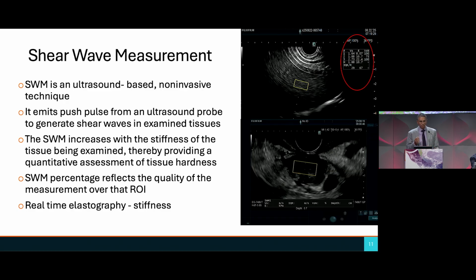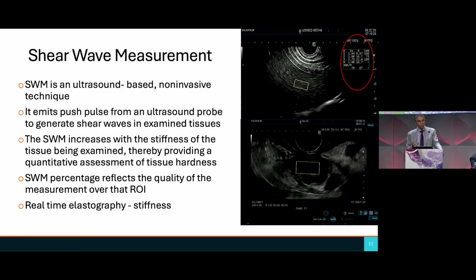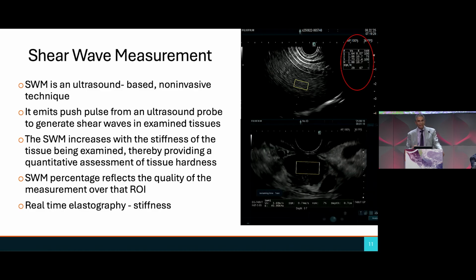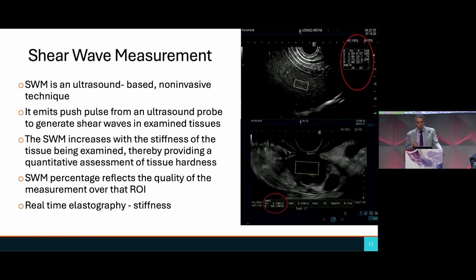But there's also this quantity that's the shear wave measurement percentage, the VSN. And what that tells us is the quality of those shear wave measurements. And we really want this to be over 50%. In fact, Rob and Cham in their book talk about having that value over 60% to understand the uniformity of that lesion. Well, one thing that we know about pancreatic cancers is that they're not very uniform at all. And so when we perform shear wave measurement with this, what you can see is we may get higher shear wave measurement results, but that VSN is actually very low, suggesting that the quality of that measurement is not very good. And this actually has some implications that I'm going to tell you about here, that shear wave measurement percentage.